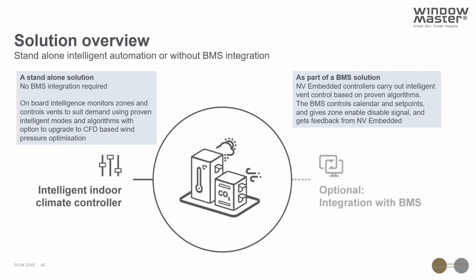It's a decentralized solution, highly stable, highly flexible, and very cost effective. NV Embedded can also be integrated as part of the BMS solution, forming part of an integrated approach. NV Embedded controllers can still deliver control of the vents, but they'll do it based on set points and instructions from the BMS to enable or disable the signal, as well as coordinating operation of the NAT vent with other systems around the building.